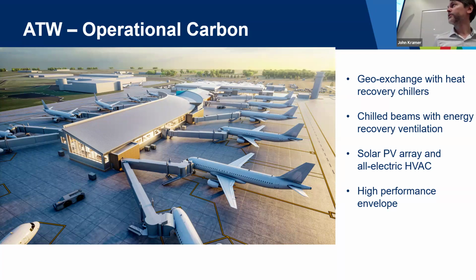And then you can see roughly, it might change from that image, but somewhere around 6 to 10 additional gates added to the project. I think currently it's at 6. So one of the measures we looked at for improving the energy efficiency, and we almost didn't even have to recommend it, the client seemed like they wanted to do it. So we're like, great. Geo-exchange, also known as a geofield or geothermal, with heat recovery chillers. That optimizes your condenser loop so you're just using ground temperatures to reject heat to or extract heat from, depending on if you're heating or cooling.